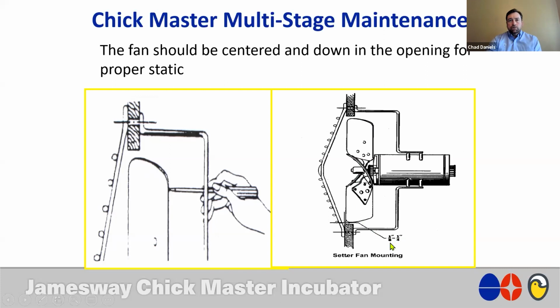So when you look at these dimensions, what you're physically looking for is a distance of anywhere from 1/8 to 1/4 of an inch from the tip of the blade down to the fan guard. So it's important to get that spacing correct. This is a big key issue.